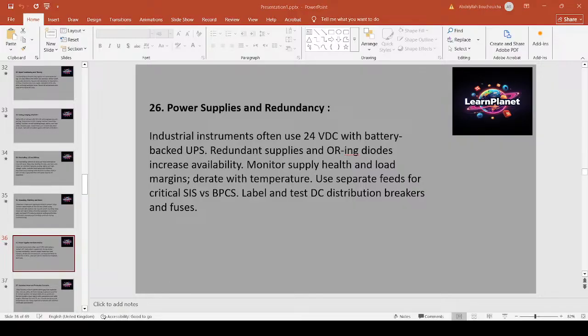24 VDC is the standard for field instruments, backed with UPS and redundant supplies for critical loops like SIS emergency valves. Use OR-ing diodes or load sharing modules to provide hot redundancy and avoid single point failures. Monitor supply voltage and current and leave headroom to avoid brownouts when loads change. Segregate critical SIS supplies from BPCS to meet safety, separation, and availability targets.